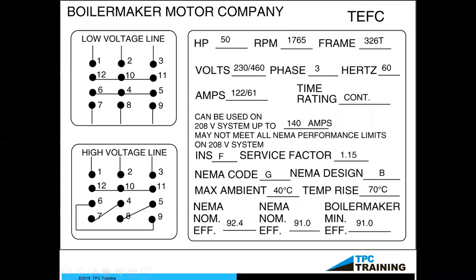So we're looking at a nameplate here, and we can see a 50 horsepower motor right up at the very top. The first thing that goes through my mind when we hear 50 horsepower motor is that it is a very heavy motor. So we're looking at 800-900 pounds at a minimum. Notice that the revolutions per minute, the RPM, is 1765. So immediately I know this is a four pole motor because the magnetic field is spinning at 1800 RPM, but the rotor itself is only turning at 1765, and the difference is what we call slip. And an induction motor really never quite catches up to that magnetic field. And when we have that phenomenon, that gives us our rotation. It allows that north and south to attract and bring the rotor right with it.